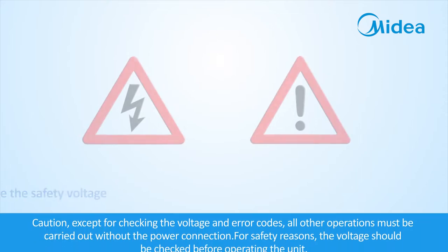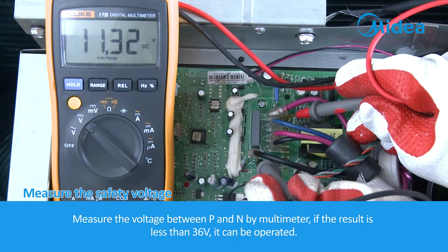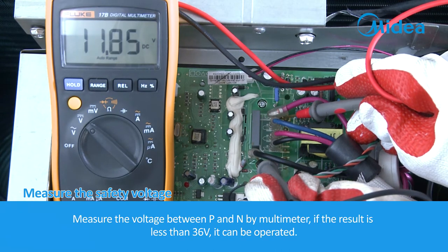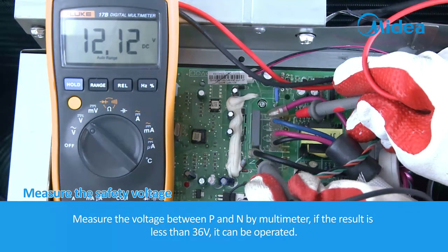Measure the safety voltage. Caution! Except for checking the voltage and error codes, all other operations must be carried out without the power connection. For safety reasons, the voltage should be checked before operating the unit. Measure the voltage between P and N by multimeter. If the result is less than 36 volts, it can be operated.